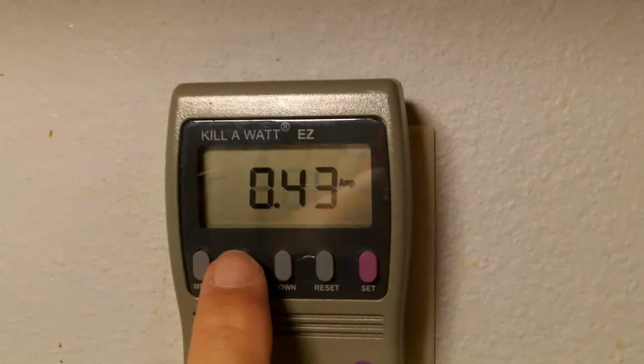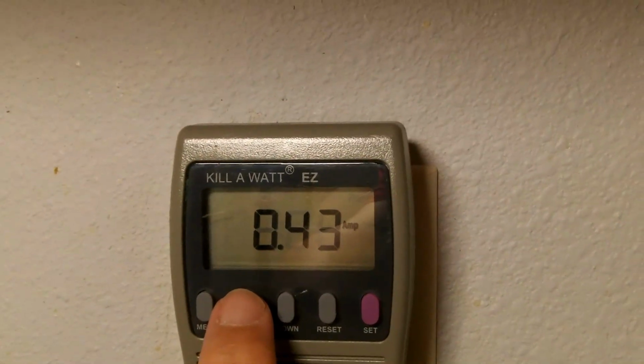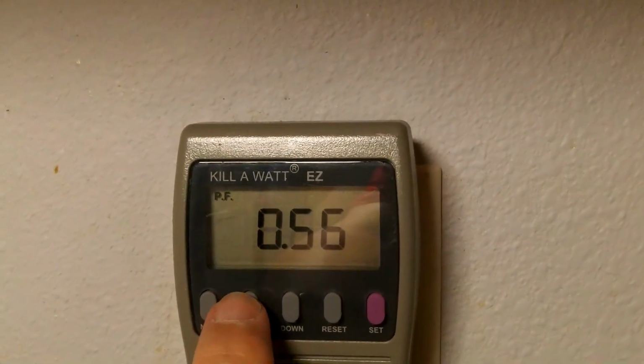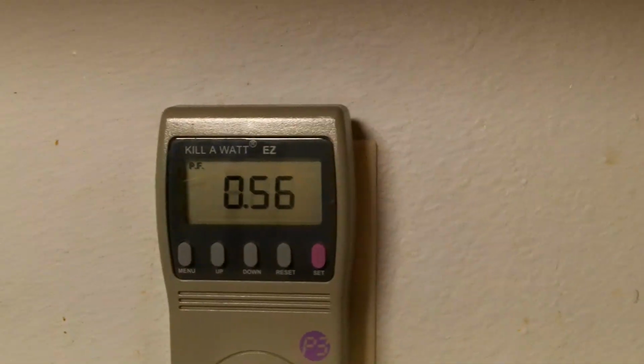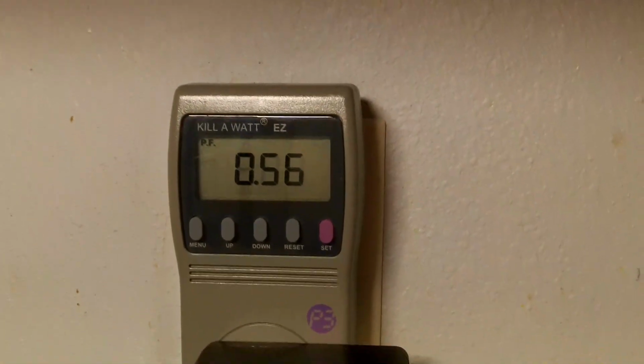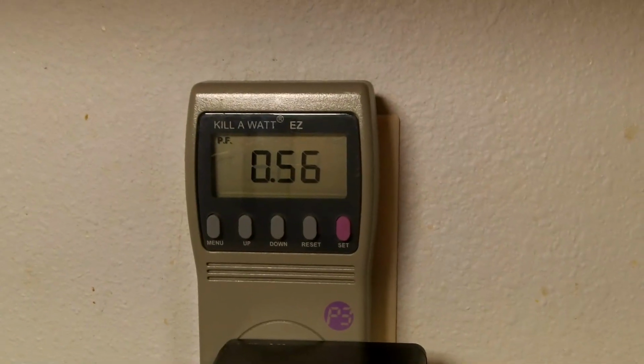On the AC side, that's less than half an amp draw at 120 volts. In operation, the power factor is 0.56, but that doesn't really matter at such a low amp draw.